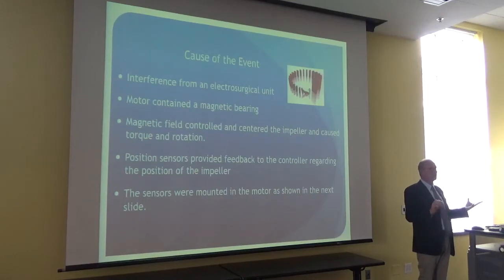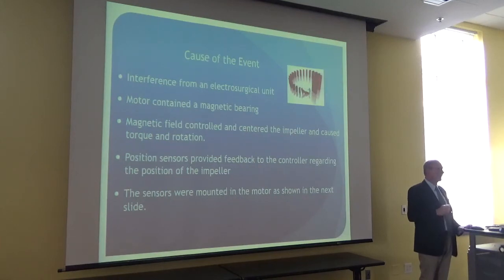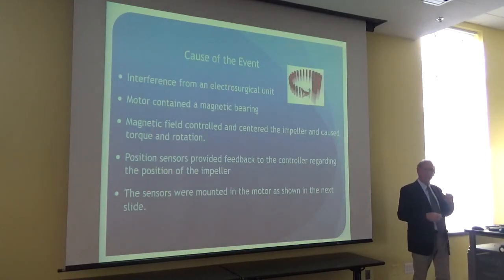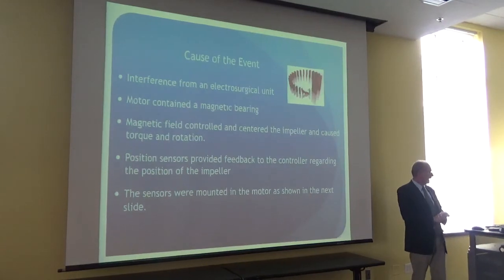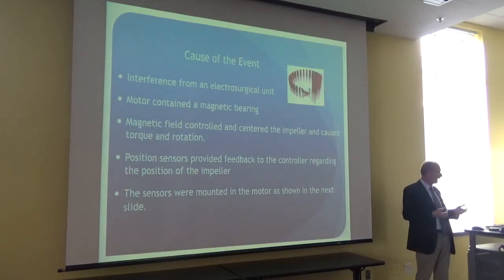In other words, the patient had some bleeding, they had an electrocautery or electrosurgical unit there, they're using the wand, if you will, to stop the bleeding, do the electrocautery. Somehow when they turned that on, it was interfering with our device. So we had a motor, as you know, that contained a magnetic bearing. That magnetic field controlled and centered the impeller and caused it to rotate and impart torque.